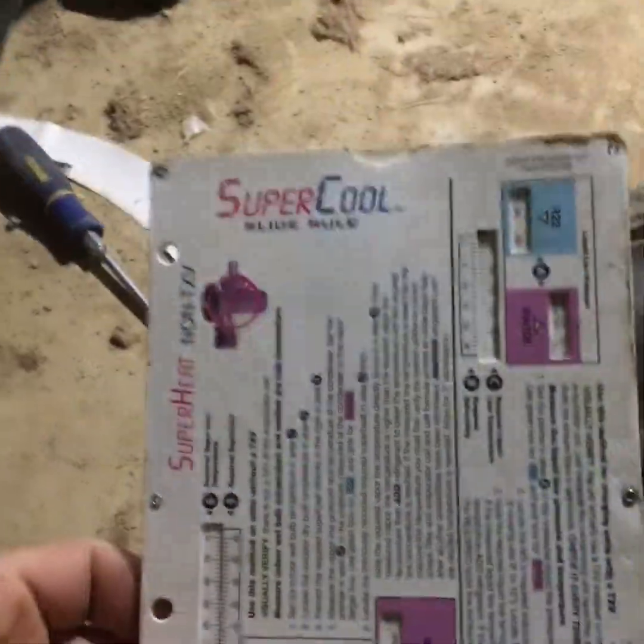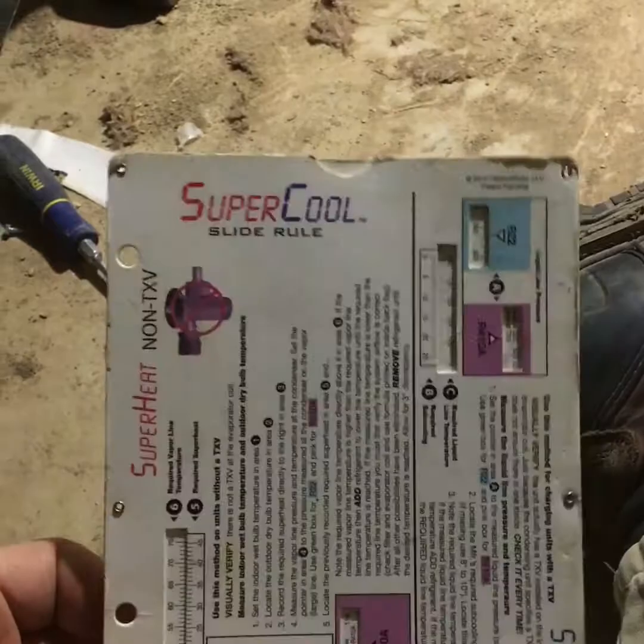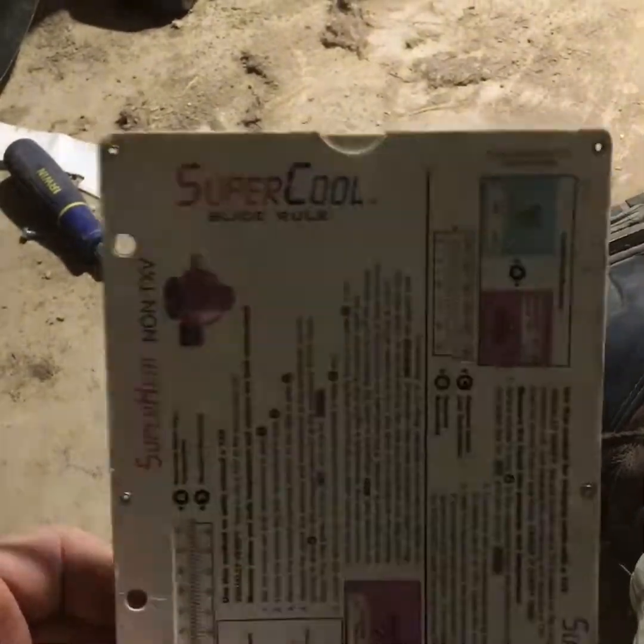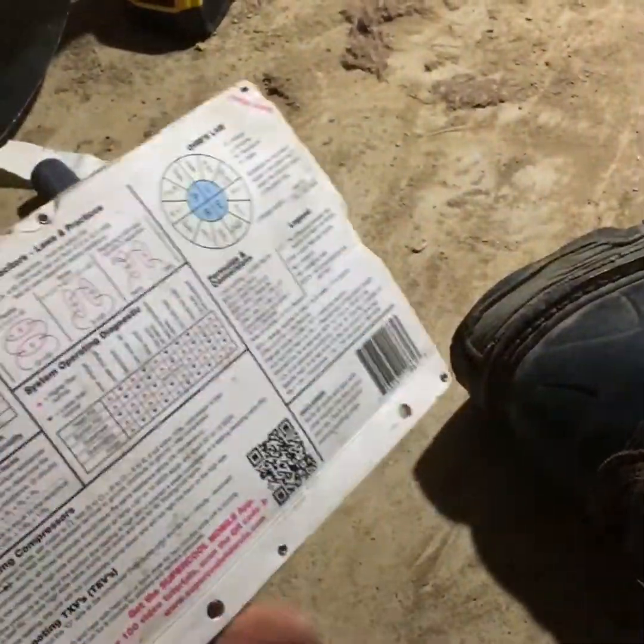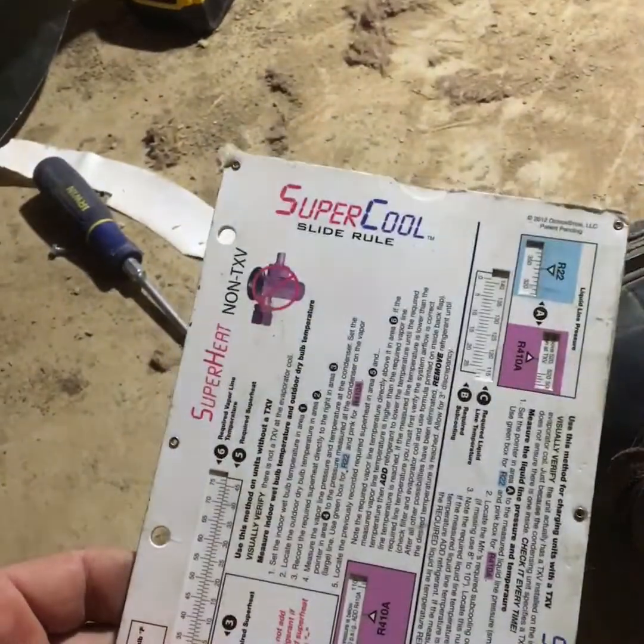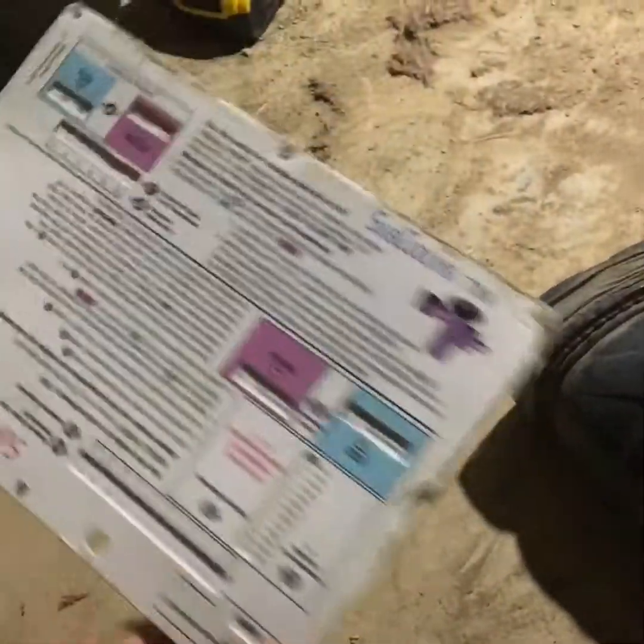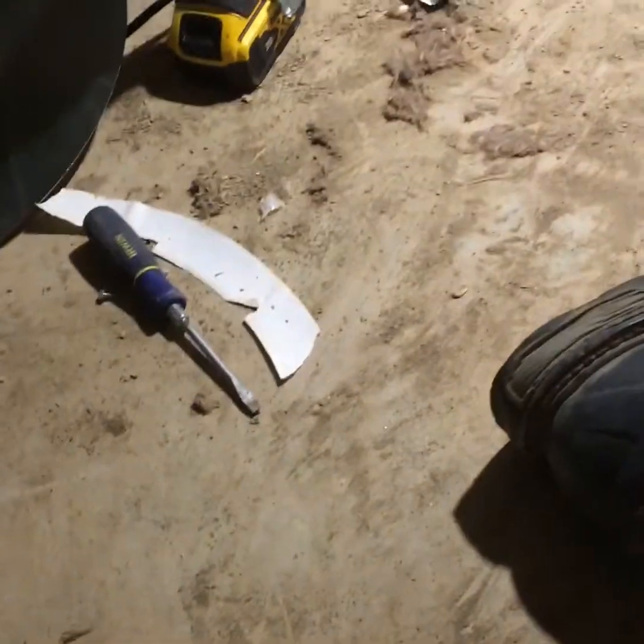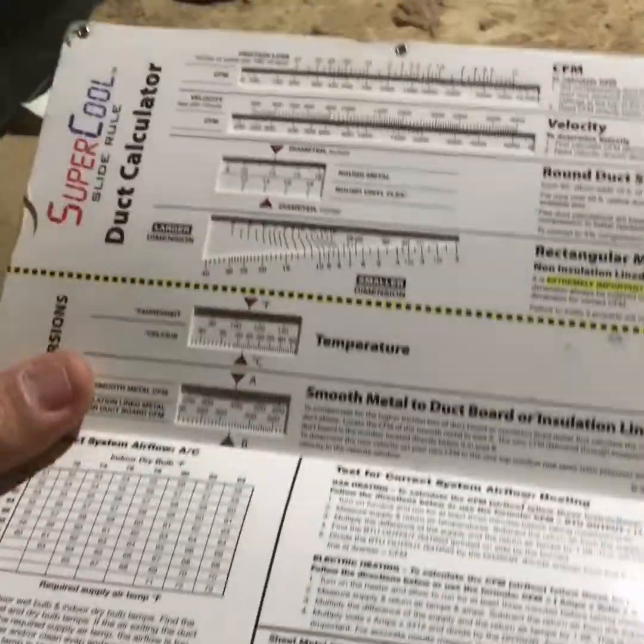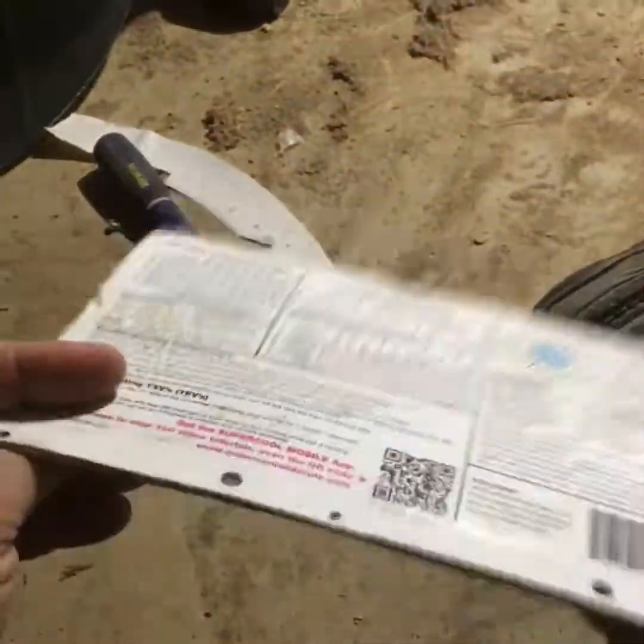If you are the owner of a company, I would buy several, put one in every truck. My technicians, when I used to run my own company, I had one in all my trucks, and that way, if they ran into an issue, I can kind of pull this out and walk them through it using these. They do superheat, subcooling. You've got all your different formulas inside for checking airflow, your heat strip formulas. You've got an up-down chart in there for troubleshooting. These are super nice, and for 20 bucks, worth every penny.